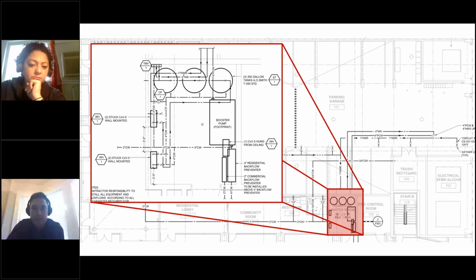So the issue to address right now is the overcooling of the boiler room. What we did initially was install a louver system and an exhaust fan adjacent to the garage to pull the hot air from the garage into the room so that the pumps didn't overcool the room, and then any excess air would be expelled through louvers in the entrance door on the bottom part of the room. But after a long, very educational session, we're taking a second look at the heat pump location and trying to revisit the air exchange between the rooms, and we might actually reconsider moving our heat pumps out into the garage.